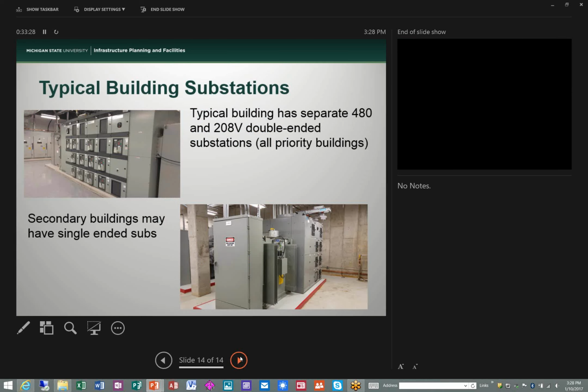So any questions at this point? Mike Anthony here. It seems to me that your preferred way of feeding a building is at medium voltage with a dry type substation somewhere in the building. Is there a load criteria? Here's what I'm getting at. Very often in campus environments, you may find lower power densities. An entirely new building may only have a computed load of 338 kilowatts, and that can easily be fed at 480 volts, say at less than 1,000 feet. I'm curious to know if you have a practice of extending 480 volt feeders to feed moderate to small size load centers or buildings.